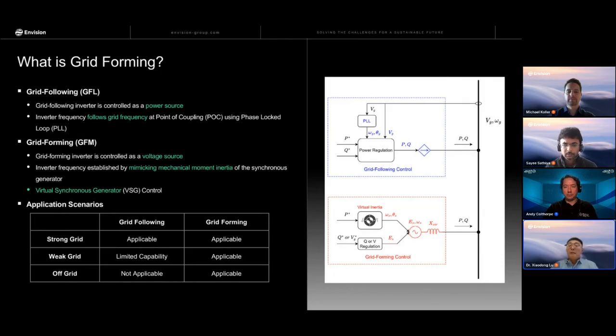So let's talk about the application scenarios. Grid following, for sure, can be applied to the strong grid. When it's applied to the weak grid, the capability is limited, especially when the short circuit ratio is less than 2. And grid forming, we can use in strong grid, weak grid, or off grid.